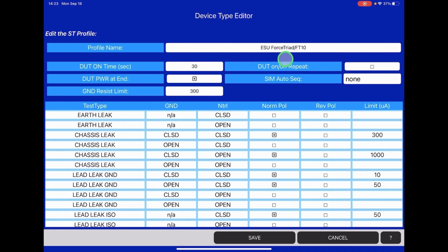The next thing you want to do is select DUT on-off repeat, whether you want to turn that on or off. This requires you to do the safety testing twice, once with the unit off and then again with the unit on if you have this box checked. In our case, for this device, we only need to do it with the device on. So we'll leave that off. The next field is DUT power at end. We always recommend you enable this field, as this will allow the power plug to remain energized after the safety testing, leaving the ESU unit powered on if we want to do any functional test afterwards. Sim auto sequence is for simulation. Of course, we don't need to do that, so we'll leave that off.